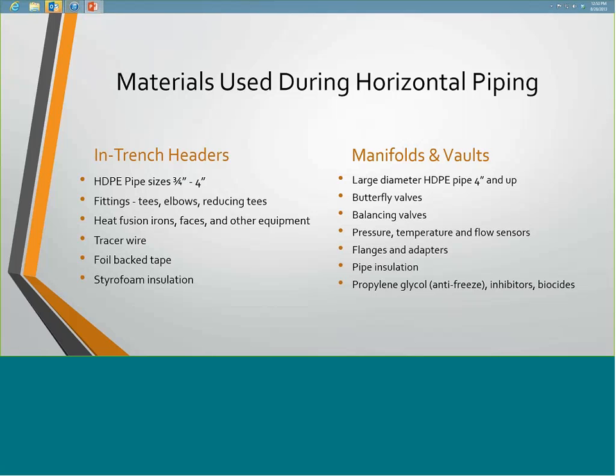A lot of these systems are water-filled. When you get into more northern climates where they're extracting more heat from the system, they may even add an antifreeze, typically propylene glycol. We'll end up using propylene glycol by the tankerful. It's nice because it's usually already stocked full of inhibitors, and propylene glycol by itself in higher concentrations acts as a biocide or bacterial inhibitor at minimum.